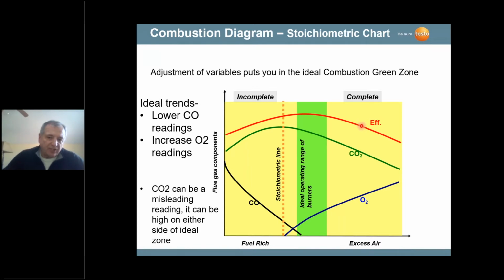So we're sacrificing efficiency, but we have a very safe combustion process because we minimize the CO, the carbon monoxide, down to maybe less than 10 ppm, 15 ppm. A typical commercial boiler operates around 100 or less parts per million going out to stack gases, okay? So if you look here, if we adjust the air and fuel, we're moving to the right, you'll see that oxygen goes up, CO2 comes down, we start losing efficiency. This here, called the stoichiometric line, separates incomplete and complete combustion.